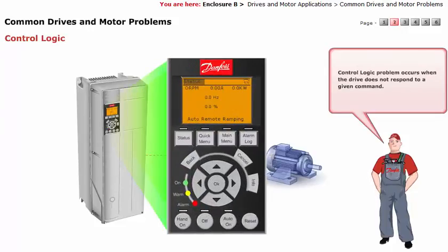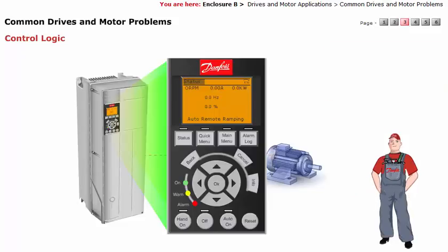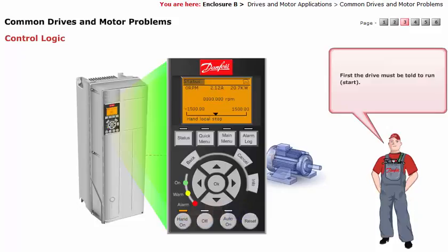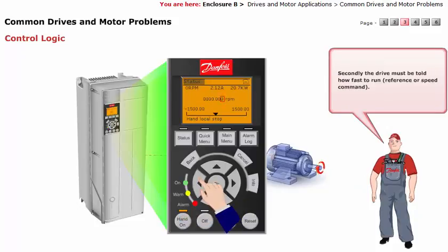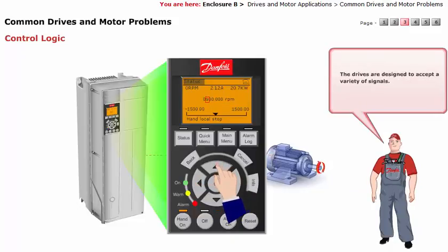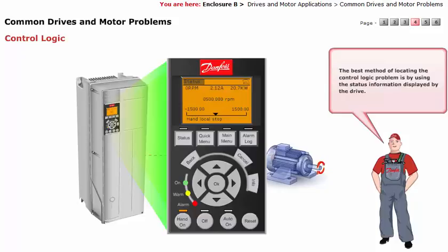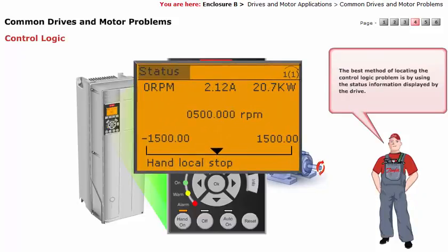A control logic problem occurs when the drive does not respond to a given command. There are two basic commands that must be given to any drive in order to obtain an output: first, the drive must be told to run; second, the drive must be told how fast to run. The drives are designed to accept a variety of signals. The best method of locating a control logic problem is by using the status information displayed by the drive. The presence of a correct reading indicates that the desired signal is detected by the microprocessor of the drive.